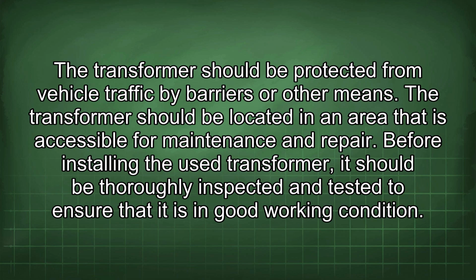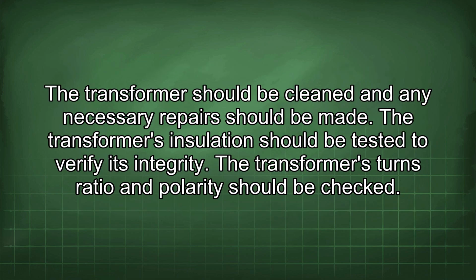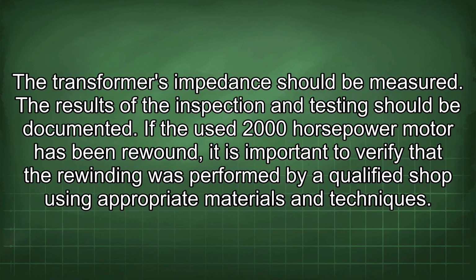Before installing the used transformer, it should be thoroughly inspected and tested to ensure that it is in good working condition. The transformer should be cleaned and any necessary repairs should be made. The transformer's insulation should be tested to verify its integrity. The transformer's turns ratio and polarity should be checked. The transformer's impedance should be measured. The results of the inspection and testing should be documented.